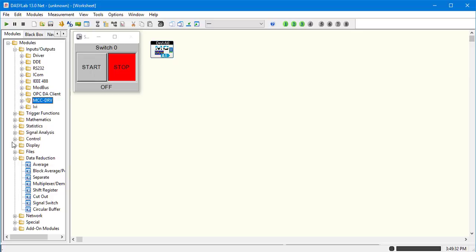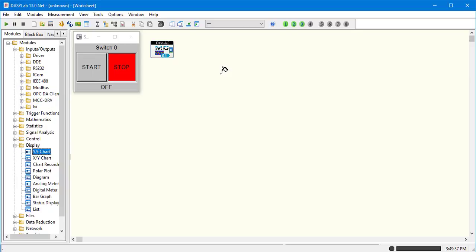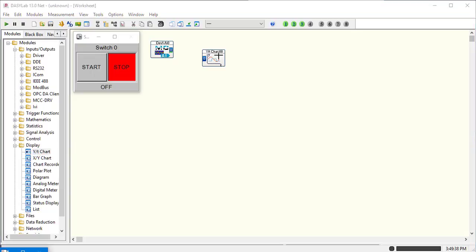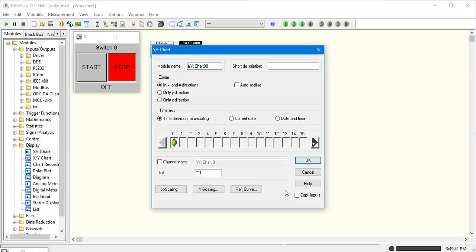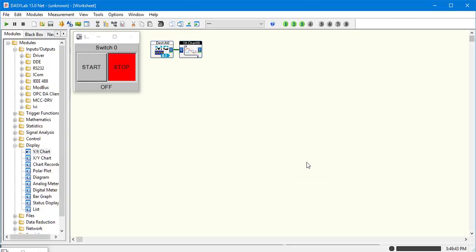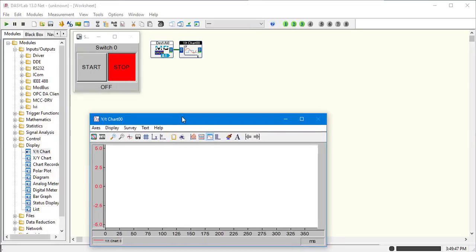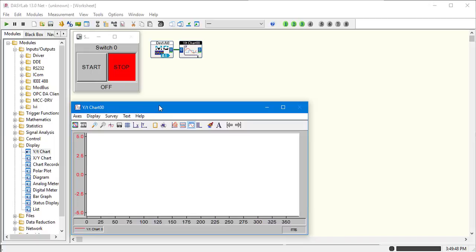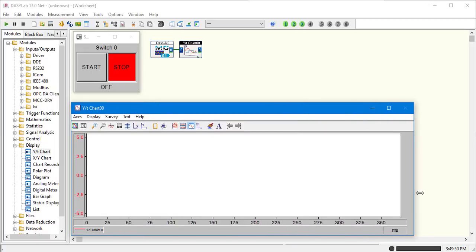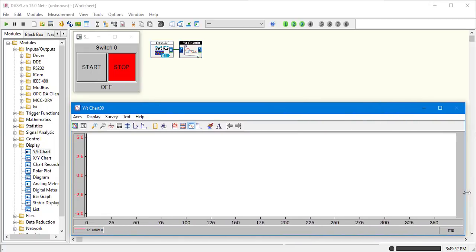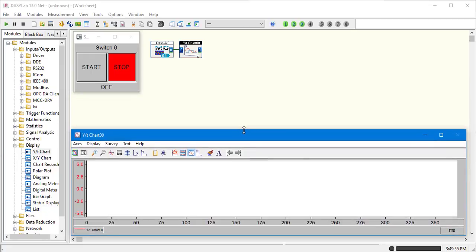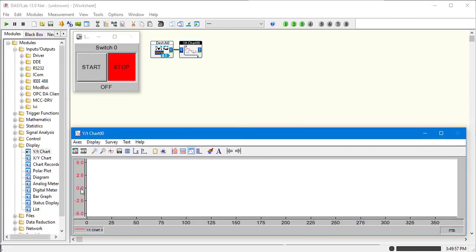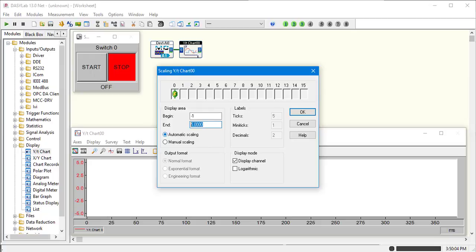Next we'll do a YT chart to display the signal that's coming in. We'll copy the inputs on that. Go ahead and start displaying these as we go. Drag them around. Typically, I start off at negative 1 and go to 5. Most of our sensor signals will be in that range.